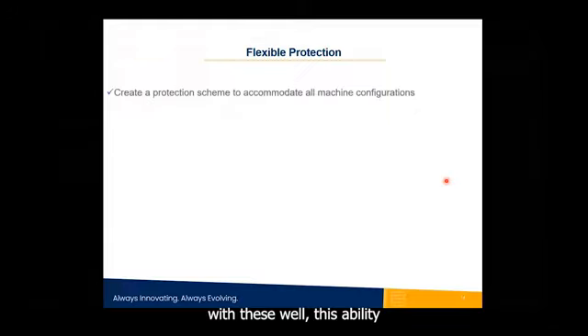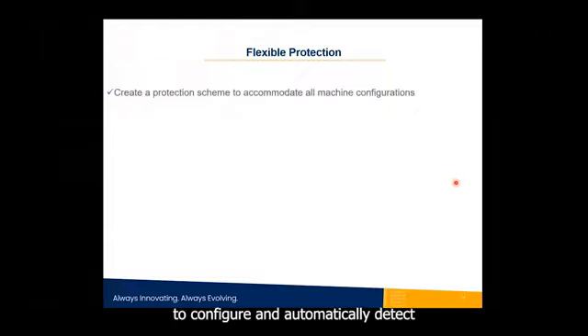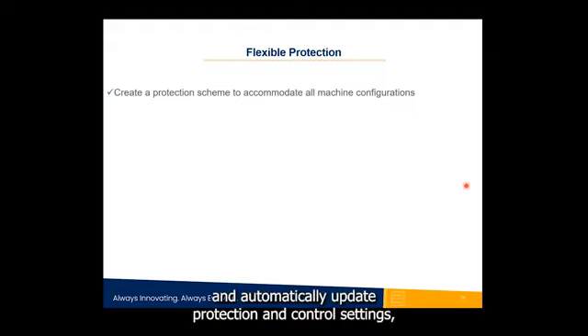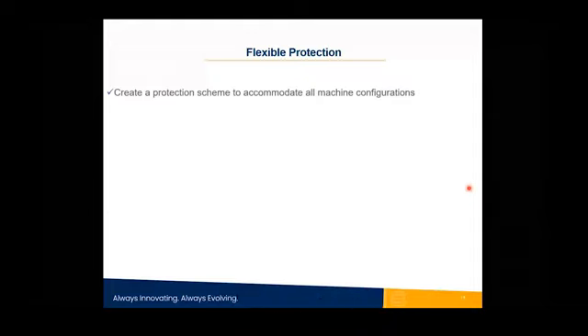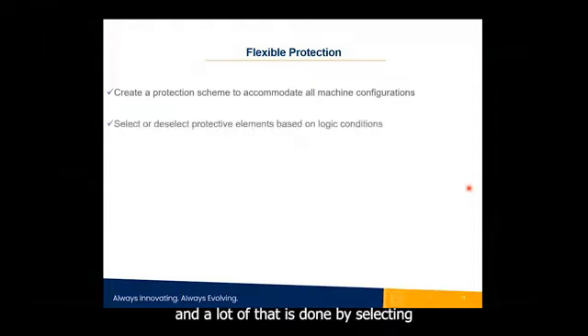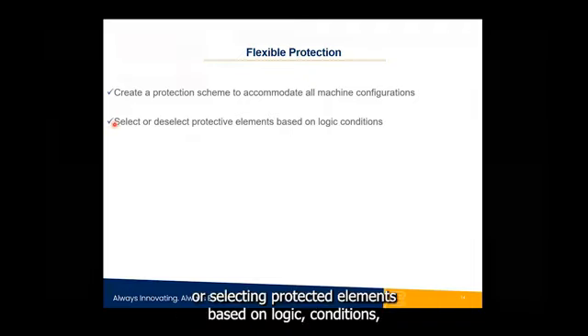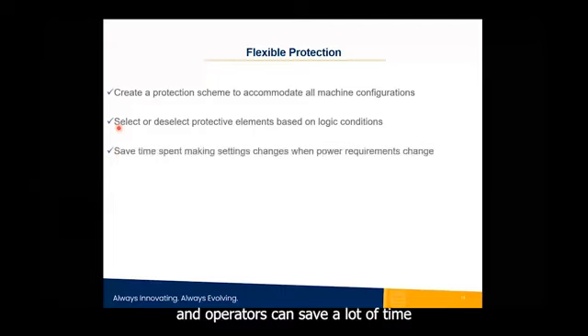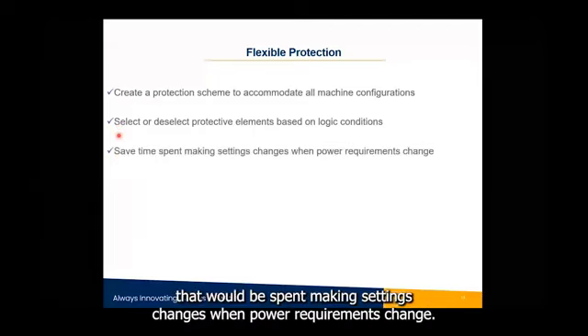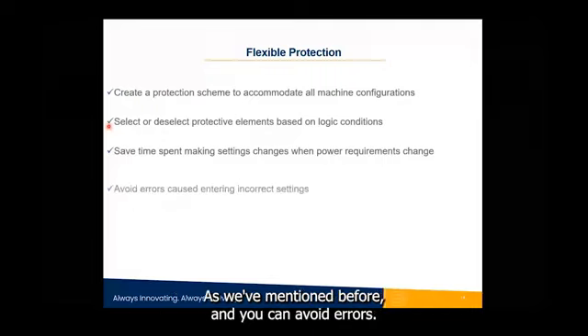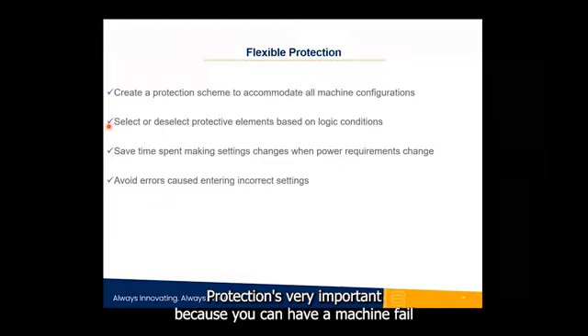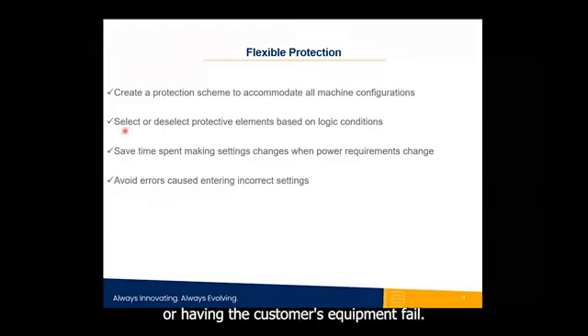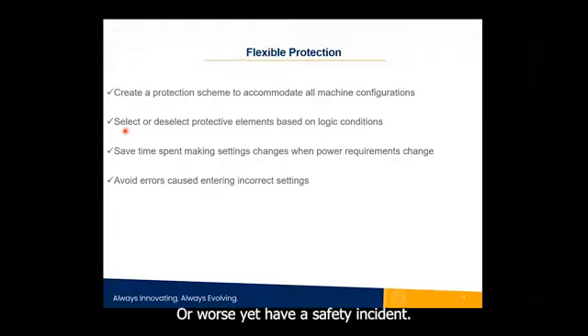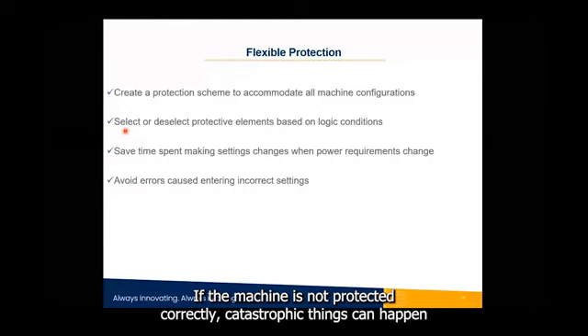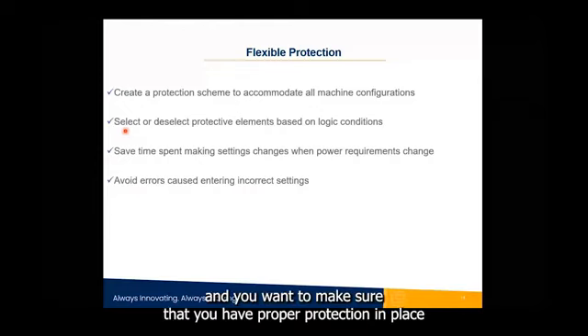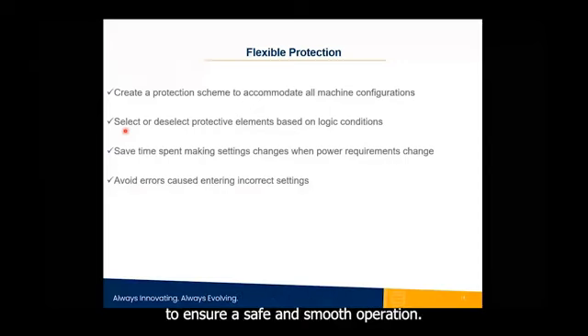With this ability to configure and automatically detect and automatically update protection and control settings, you can accommodate all machine configurations. A lot of that is done by selecting or deselecting protective elements based on logic conditions. Operators can save a lot of time that would be spent making settings changes when power requirements change, as we mentioned before, and you can avoid errors. Protection is very important because you can have a machine fail or have the customer's equipment fail, or worse yet, have a safety incident if the machine is not protected correctly. Catastrophic things can happen, and you want to make sure that you have proper protection in place to ensure a safe and smooth operation.